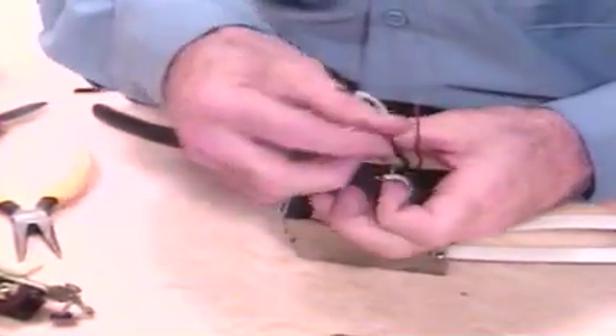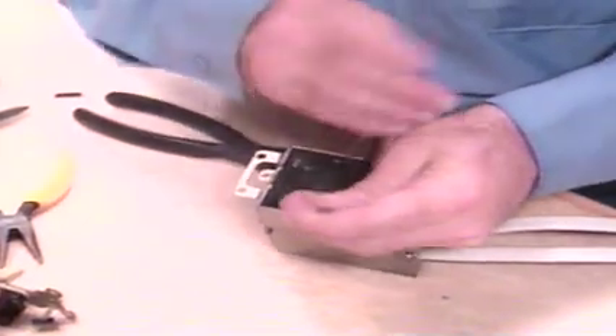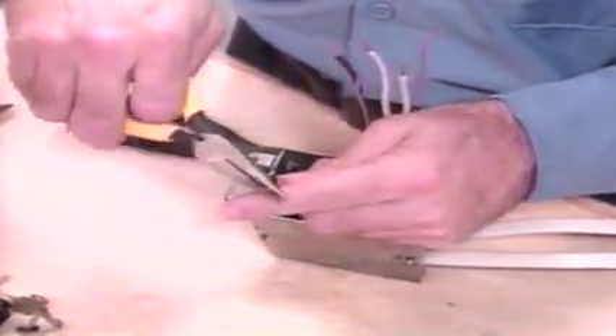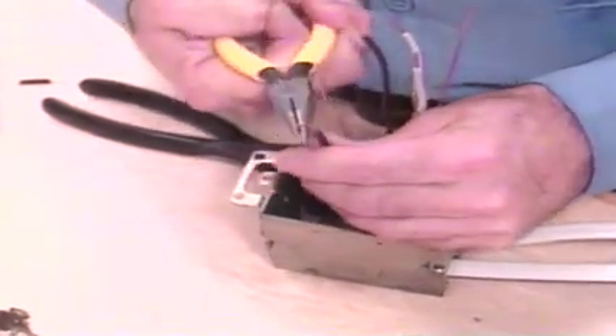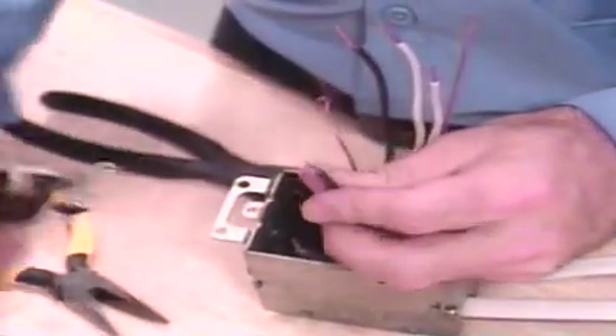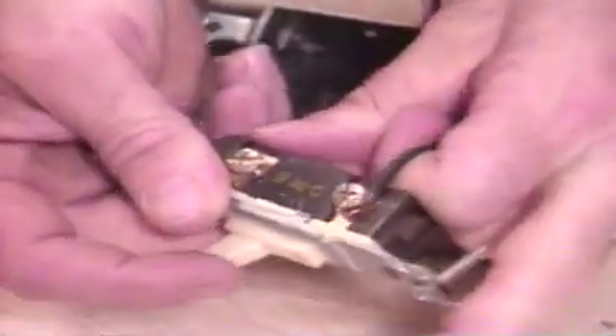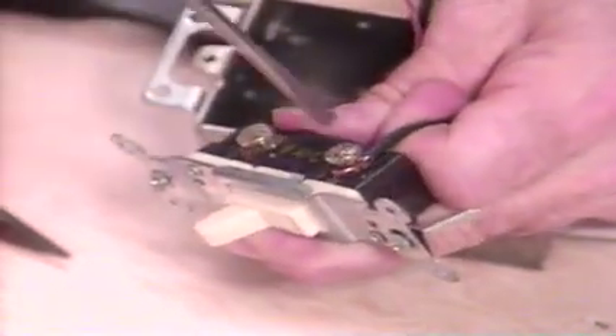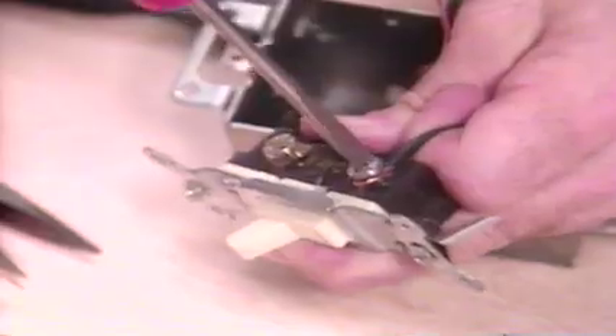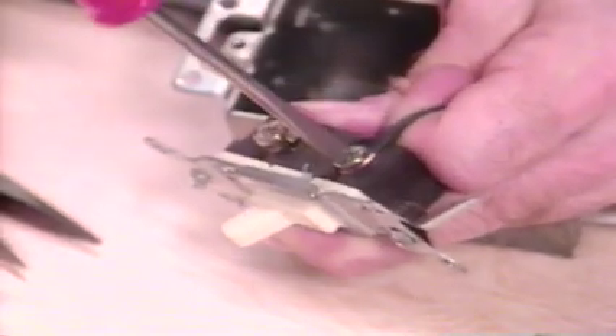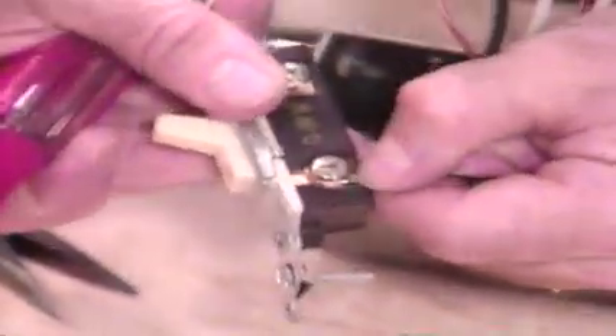Then you take the needle nose pliers and you form a little U at the end of the black wire, just like that. All right. And on the gold nut on the end, hang one of the wires. Which way do you go? Clockwise. Always clockwise. As you tighten it down, it'll pull itself in tighter. Make sure it's secure. Make sure you don't have any insulation in behind the nut. All right. Do the same thing with the other one.